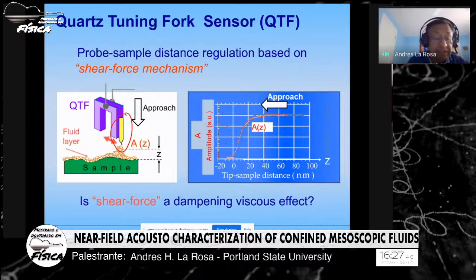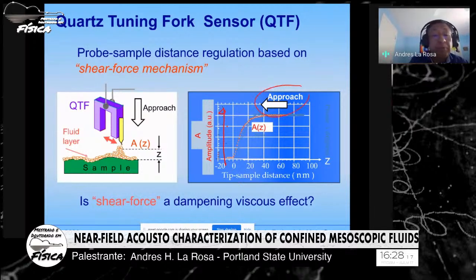There are methods to make this probe very sharp, and therefore we shake it laterally. We expect that, because of the interaction between the probe and the sample, that will affect the lateral motion of the probe. So in this case, we monitor the amplitude right here on this axis. This is the amplitude. And then we approach the sample. When the probe approaches the sample, we observe that indeed the amplitude, you see right here, decreases as you are approaching the surface.